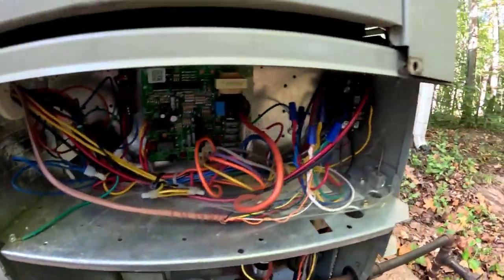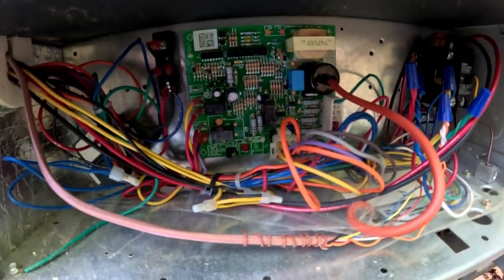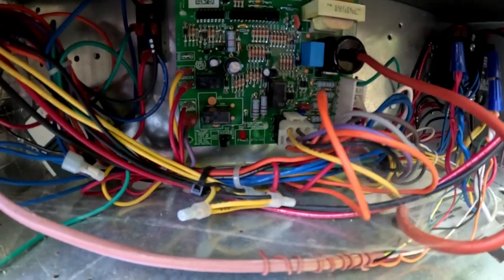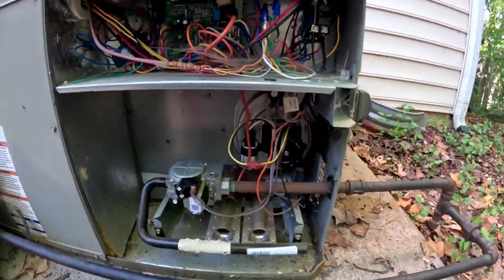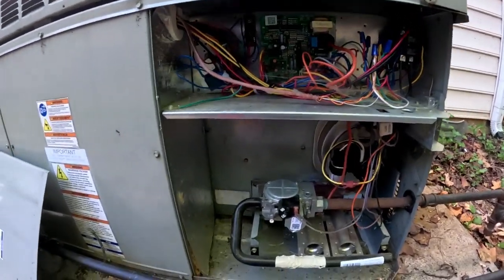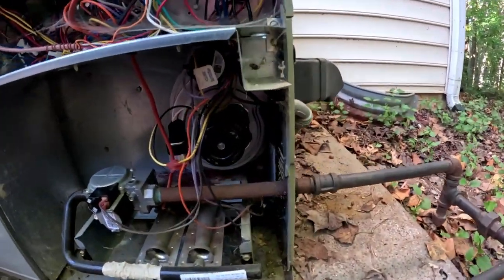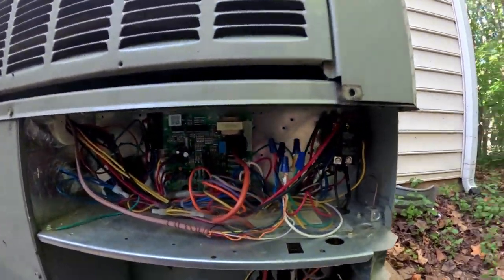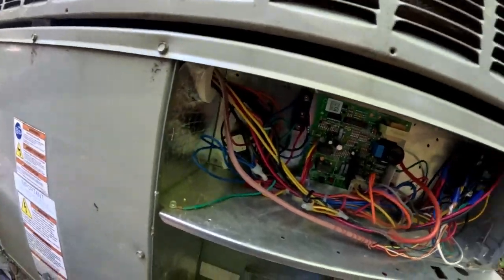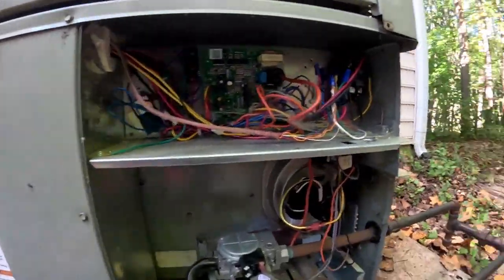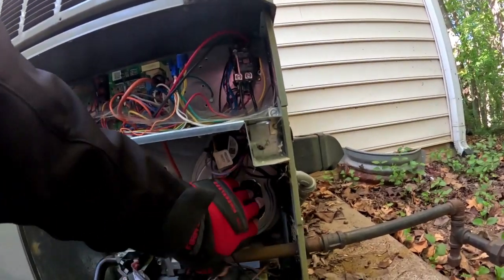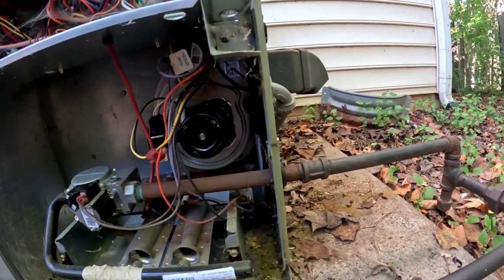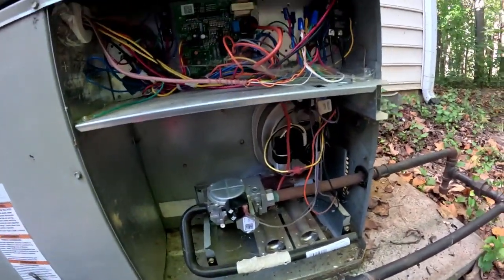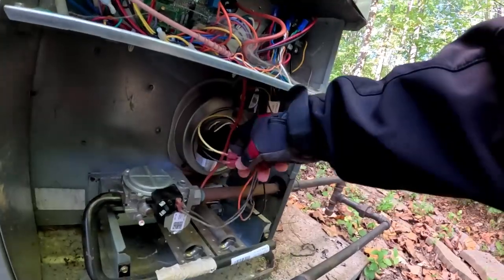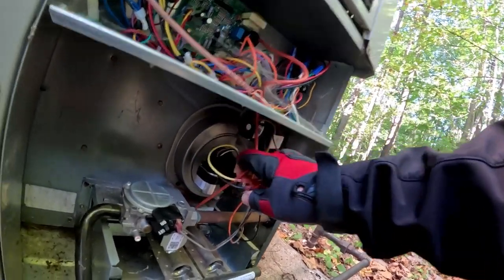So, a new Trane package unit. We have a steady flash right there, which is normal operation. The thermostat is off. I just wanted to do a quick visual on it before I turned it on. I usually do that when they say something about a burning type smell, something along those lines. They did say that this combustion motor has been replaced recently, so that shouldn't be the problem. Don't see anything in there that looks smoked up.